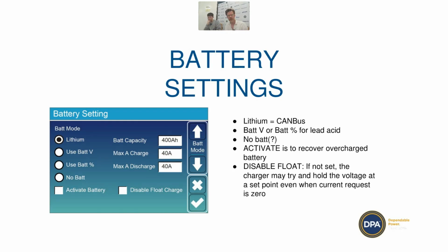So this is a global override, which is going to set what the maximum DC current in and out of the battery will be for the system. If the CAN bus requests a lower maximum charge or discharge, then the inverter will use the lower value. But if you set a lower value here than what the CAN bus ever asks for, then it will use that. So it will default to whichever value is lower. If you set the max charge as, say, 150 amps, but the CAN bus only ever says 100 amps, the inverter will only ever charge at 100 amps. When you've finished making changes, you need to tick this box at the bottom right-hand corner, and you have to do that for each page. Otherwise, it won't save your settings.